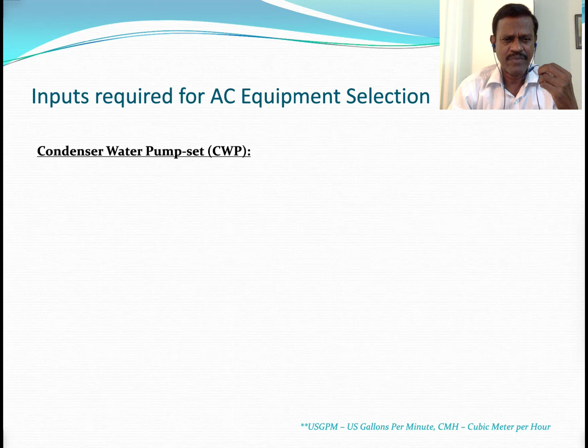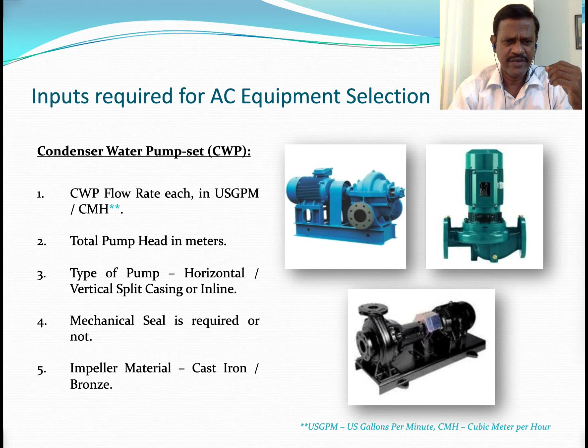Now we have seen chillers; we will talk about pump sets. First we will talk about the condenser water pump set. You have to specify the condenser water flow rate in GPM or CMH, then the total pump head in meters or feet. Then specify the type of pump: horizontal split casing, vertical split casing or inline pump. Then mechanical seal; nowadays all pumps come with a mechanical seal, but it is still better to specify it. Next, specify whether the impeller material is cast iron or bronze. Then other ancillary items like coupling guard and base plate, whether they are required or not, and give the input to the pump vendor.